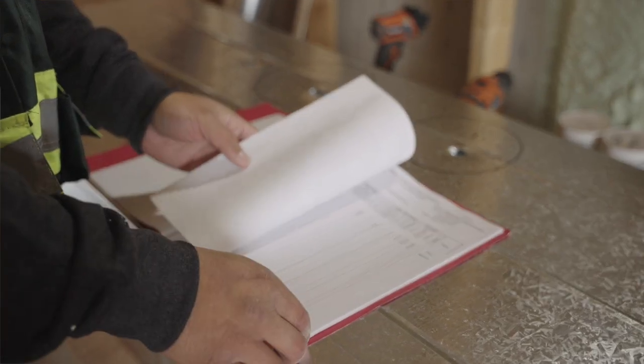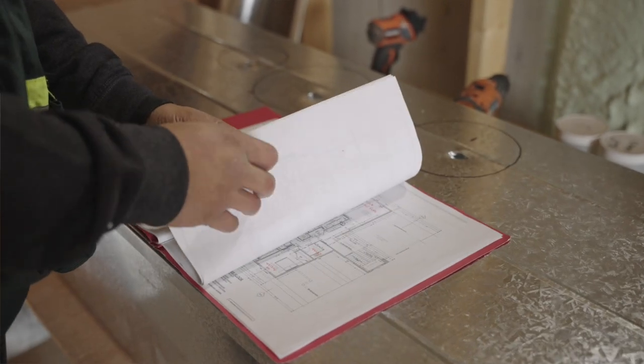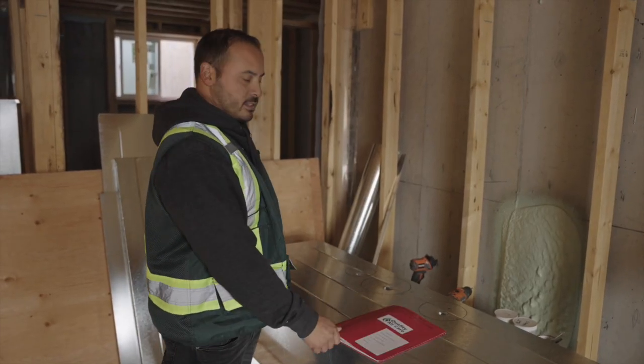The biggest and most integral part of these installations is sizing the house correctly. Every house gets a heat loss and heat gain calculation, determining the exact BTUs required for the home. This goes into a calculator, then a duct calculation, and is put onto paper. That way, it's the easiest guide for our installation team to follow, and something that stays with the home once it's turned over.